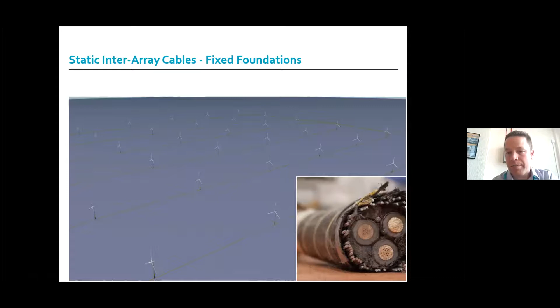We've got a static cable here with some armor wire, the cable cores, fiber optic, and that's the connection into, in this case, a monopile—a fairly simple connection. It's got a bend stiffener or bend restrictor, goes through some protection to stop it abrading on the seabed, and separated by about 2 kilometers, these cables are strung together on the wind turbines. Inside the turbine itself, the cable is connected via some joints to the switchgear.